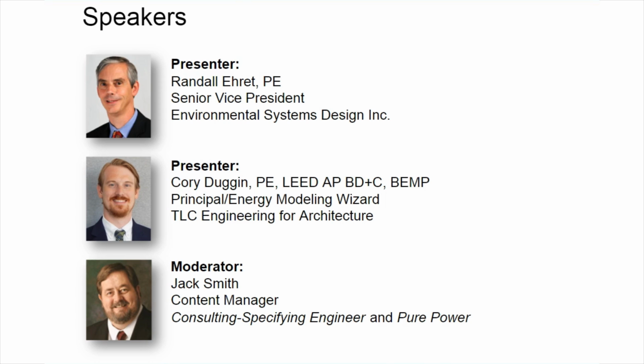Yeah. That's an interesting question, and I'm going to refer back to one of our earlier slides to help answer that. Let's go back to this slide, which is a typical emergency power system with multiple branches. When we're integrating emergency lighting and life safety systems, all of those are required to be picked up in 10 seconds or less. So typically on most buildings, we pick those up via a single transfer switch. And if we want to integrate UPS, which is always a great idea, I would typically put that on the load side of the transfer switch. It'll carry us through the outage, and then emergency power will be restored.